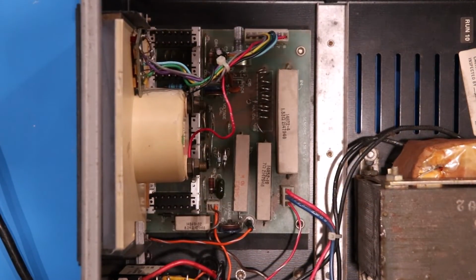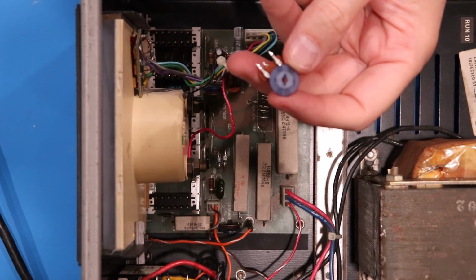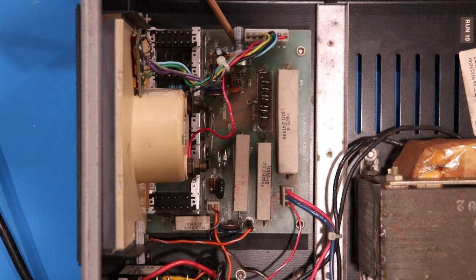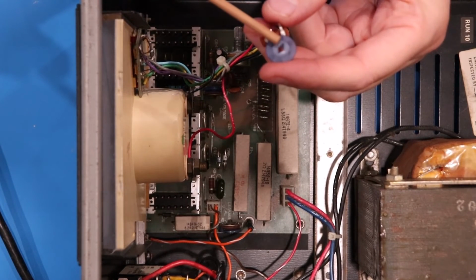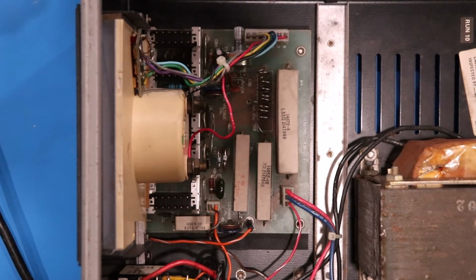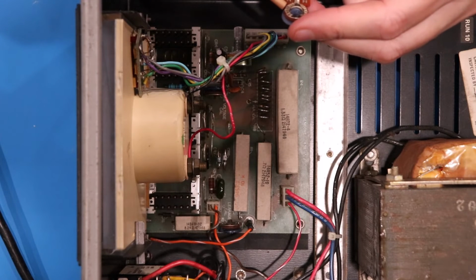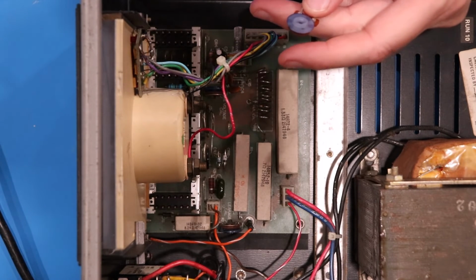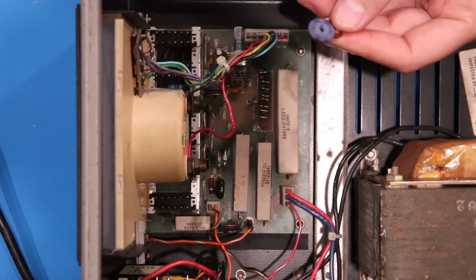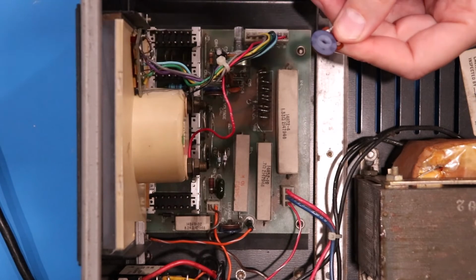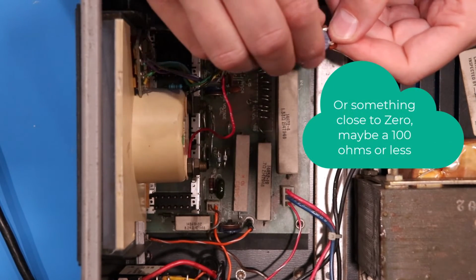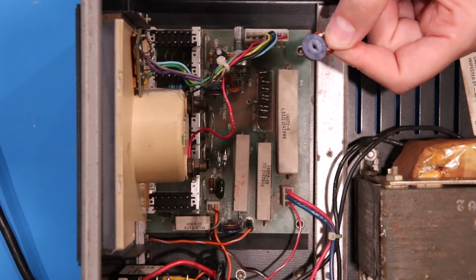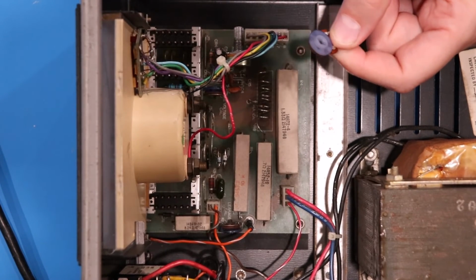As in life, nothing is simple. So then I went to this little potentiometer, which, by the way, did look like this, and tried to adjust the 1.5 amp current setting. There again, couldn't get it in range. Guess what? This unit itself turned out to be the problem. It had gone out of whack. It would not go any lower. So on one end, when you swing a potentiometer like this, it should go all the way to 10K on one end, and theoretically all the way down to zero resistance on the other. This one would go to 9.4K on one end and around 685 ohms on the other end. Could not get it down to zero.